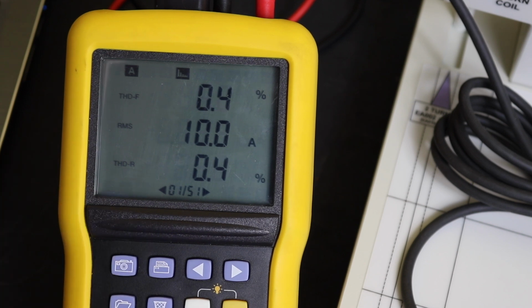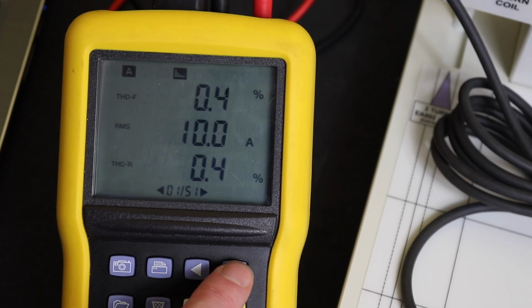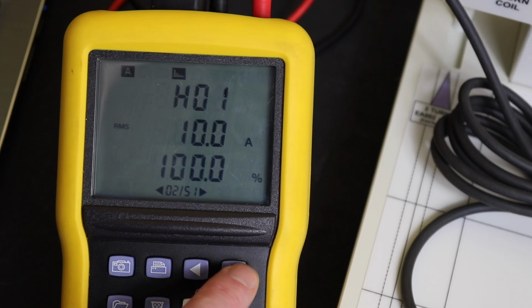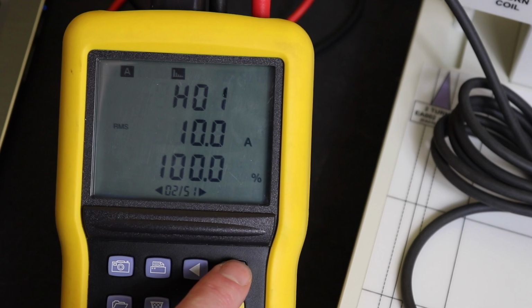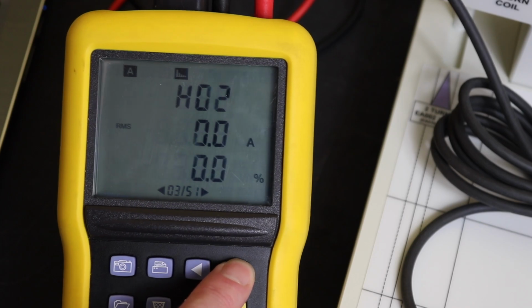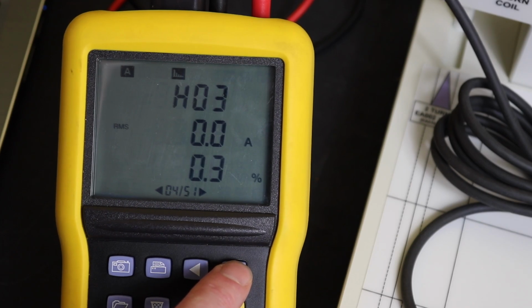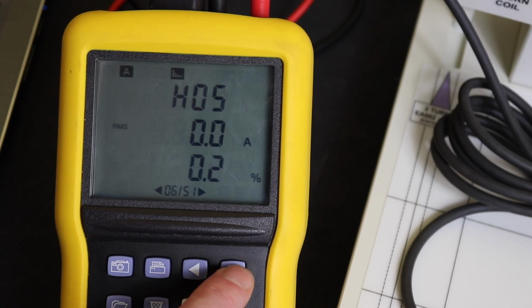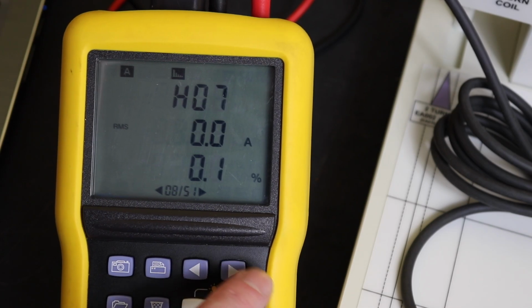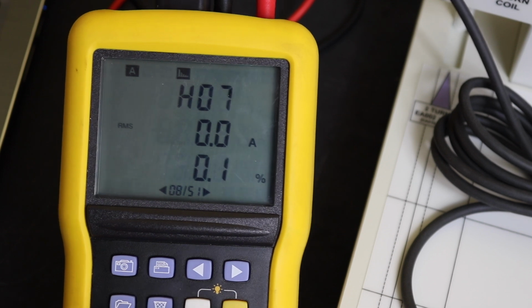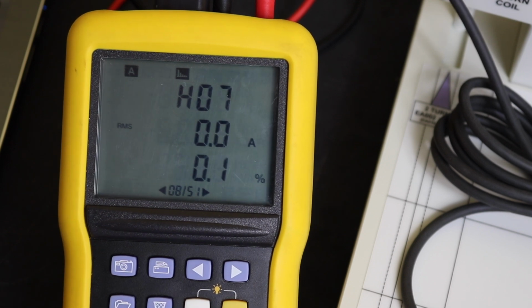Let's return back to the original screen. We've got 10 amps going in, and total harmonic distortion is 0.4%, so a bit more distortion on the amperage. And we can move through them. And again, there's our harmonic 1, which is 100%. Yeah, looks like we've got slight odd harmonics it's picking up. Little bits. Yeah, okay, so all of those values are in there as well.